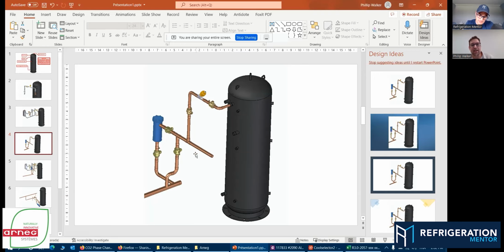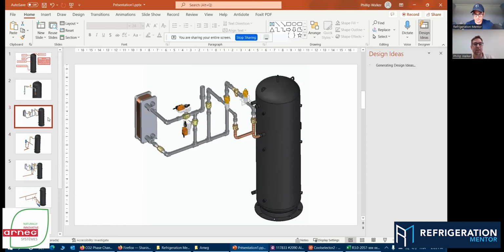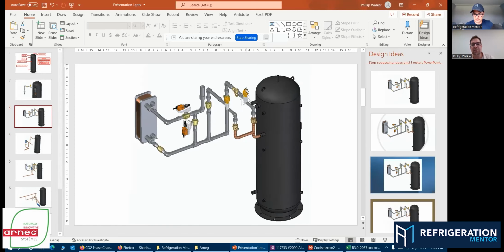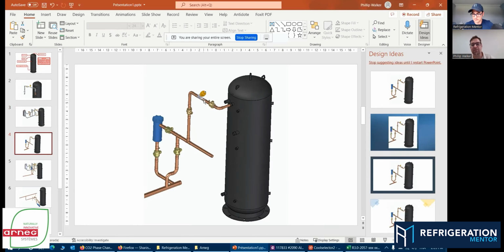So here's the flash gas bypass. So everything we just spoke about. One of the first things, myself as the designer and as a technician, my guys and myself, we look at when we go into any mechanical room for one of our machines that we've had a call on, is really what we just spoke about. We look at the drum. How's she running? We look at the valve. Everything we just spoke about here, these valves, high pressure, how the drum is running, how's the flash gas. We start there. It's the heart of the system.